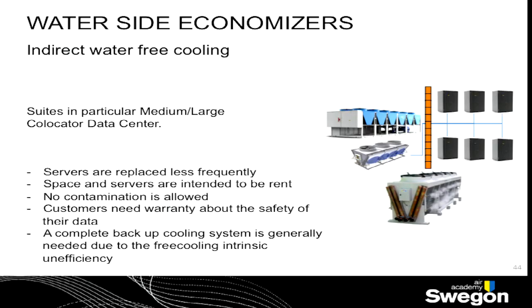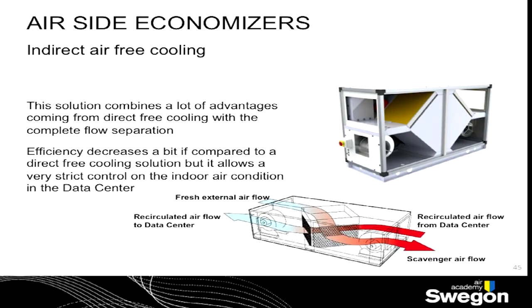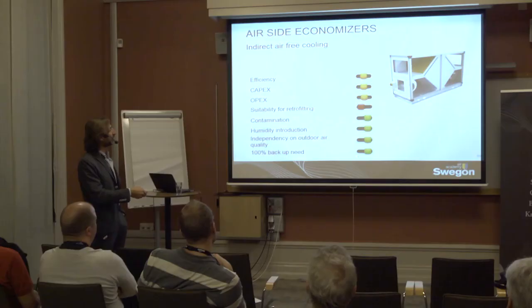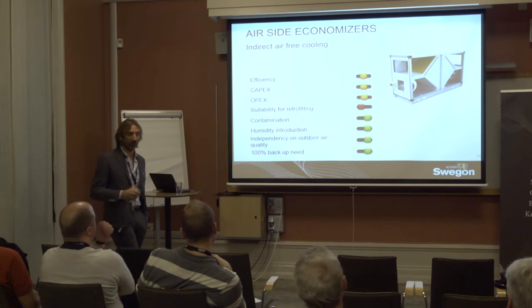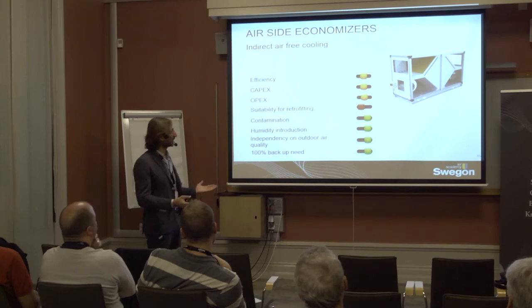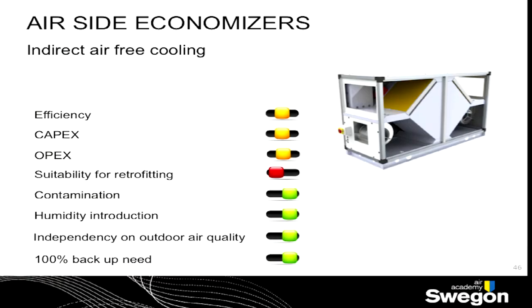The same separation we can obtain with an indirect air free cooling system where water is not used. So here the exchange is between air and air. We have, let's say, a scavenger airflow that is used only to cool down the indoor air. So we have a complete separation, and we are able to maximize the free cooling benefit. In this way, we have all the advantages coming from the separation of the fluxes. So the indoor air is completely separated from the outdoor. And we take the advantages of a system with a medium-high efficiency, of course, that can be increased with the adiabatic cooling.